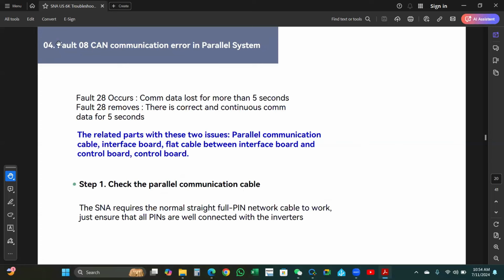Number 4, fault 08, communication error in parallel system. Fault 28 occurs when CAN data is lost for more than 5 seconds. Fault 28 is removed when correct and continuous CAN data is received for 5 seconds. The related parts with these 2 issues are the parallel communication cable, the interface board, and the flat cable between the interface board and the control board.